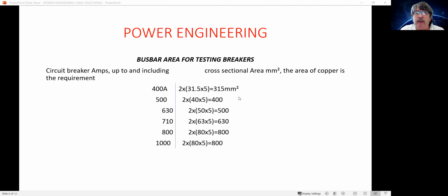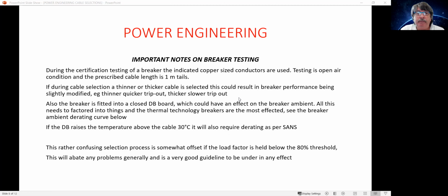So when we have a look at that, we can see immediately that circuit breaker has some net effect. The possibility is definitely there. So we need to also have a look at how these circuit breakers are tested, because this is, I think, a little bit important here in the way that it's actually tested in the certification process, because it is slightly different to what you have in the real world. Because obviously in the real world, the circuit breaker will fit in a panel of some sort, some form of holding device.